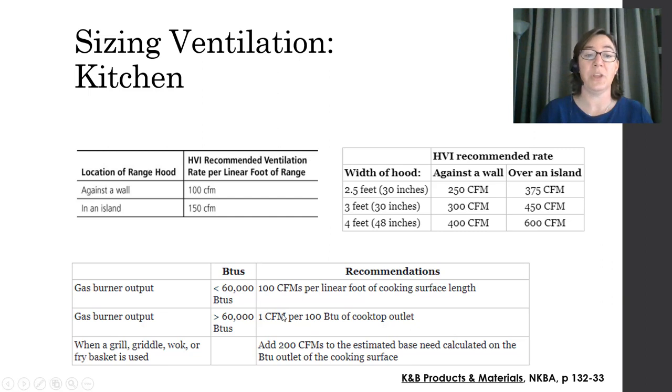Finally, you can also adjust for some accessories like a griddle, wok, or fry basket. Add an extra 200 CFM, and again, go with the calculation for the higher BTU units.